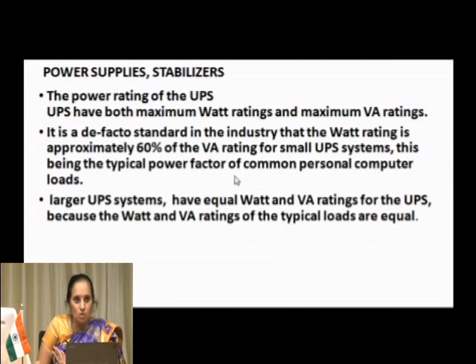So whatever load I connect to my UPS, that rating is the useful power rating, that is watt rating. But the rating which is normally given on the UPS is the VA rating, especially in small UPS systems, like what we use in our houses. So you have to take my useful power rating to be approximately 60% of the VA rating. That is one thing, and for common personal computer loads, this is the actual calculation we have to do to decide what type and rating of UPS we have to consider for the load we are going to connect.